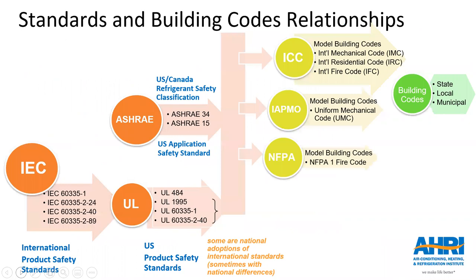So now that we understand what standards and building codes are, let's look at how they all work together, how they're all put together. Remember, I mentioned that the building codes reference standards, and standards contain the details. So in line with that, you see here that the model building codes are fed details about refrigerant safety requirements from various standards, such as shown here, ASHRAE 34, ASHRAE 15, and the various UL standards, including 2-40.